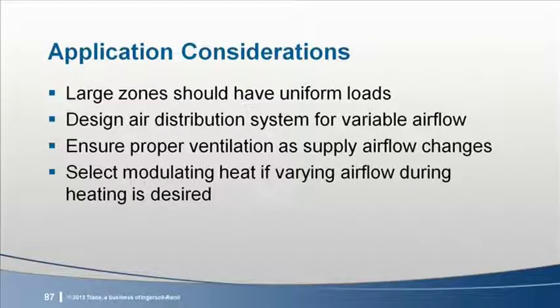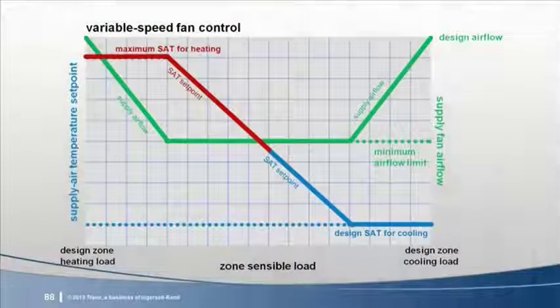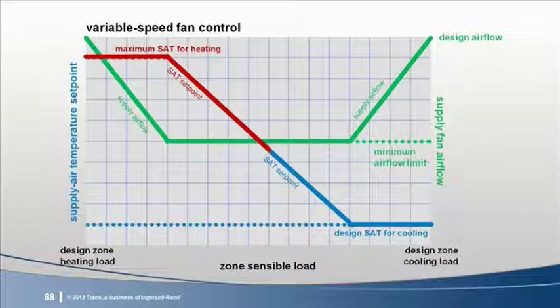But if you also want to allow variable airflow during heating operation, you probably need to use some type of modulating heat source. I showed this example control sequence earlier. The right-hand side of the chart shows variable speed operation when cooling, while the left-hand side shows variable speed operation when heating. To enable variable airflow when heating, you'll likely need to use equipment with either a modulating gas heater or a hot water heating coil. Otherwise, if the equipment has on-off gas or electric heat, the manufacturer may require the unit to operate at full airflow whenever the heater is activated. So you want to check with the manufacturer when specifying or purchasing single-zone VAV equipment.